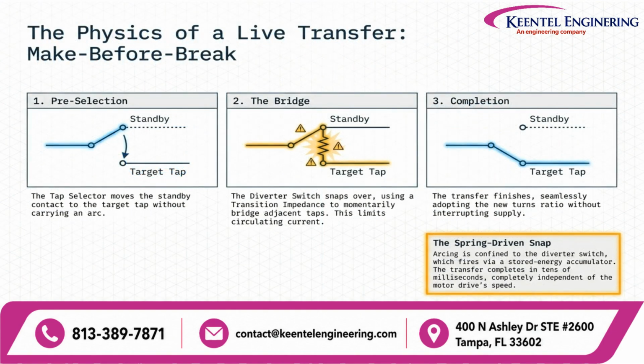Changing transformer taps while carrying load is far more complicated than simply moving a switch. The process occurs in three carefully controlled stages. First comes the pre-selection stage, where the next tap position is prepared before any electrical transition begins. Second is the bridge stage, where a transition impedance, either a resistor or reactor, temporarily carries current between the two adjacent taps. This prevents short circuits and avoids interrupting load current. Finally, the switching sequence is completed, disconnecting the old tap while maintaining uninterrupted power delivery. This make-before-break principle is the defining engineering feature of an OLTC and allows voltage regulation without service interruption.